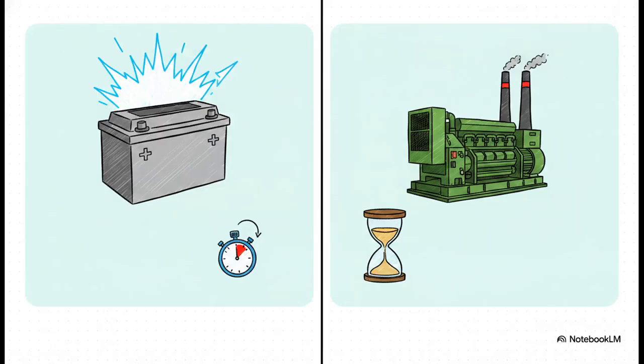What's really interesting about this slide is the deep contrast between our backup layers. The UPS is incredible because of its instant transition, but it has a fundamentally short duration. It's battery-powered and really just meant to hold the fort. Contrast that with the backup generators, which can take up to 60 seconds to automatically start and reach full output, but they offer a long-term duration because they're fueled by heavy-duty diesel engines.